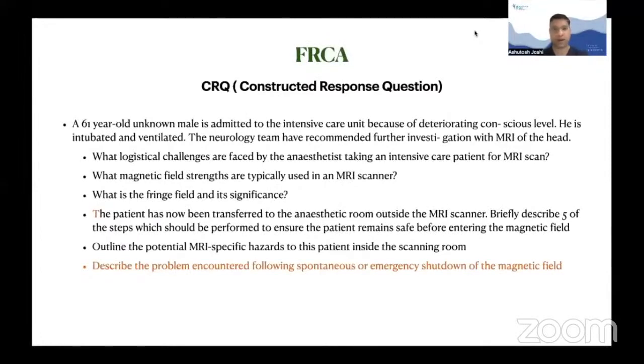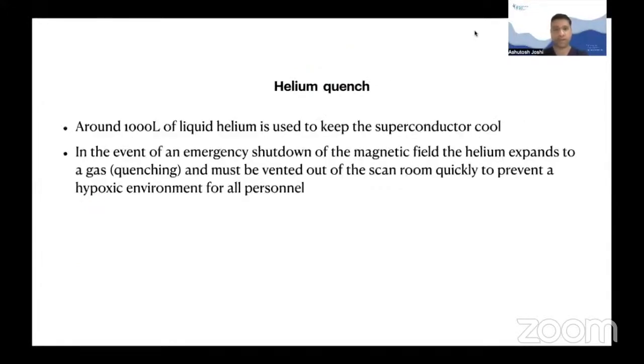Here is another question on MRI. We have gone through most of it, except describe the problem encountered following spontaneous or emergency shutdown of the magnetic field. What happens is known as helium quench, as around 1,000 liters of liquid helium is used to keep the superconductors cool. In the event of emergency shutdown, the helium expands to a gas, which is known as quenching, and must be vented out of the scan room quickly to prevent a hypoxic environment for personnel and patient.